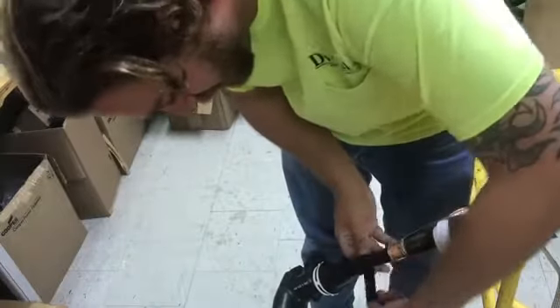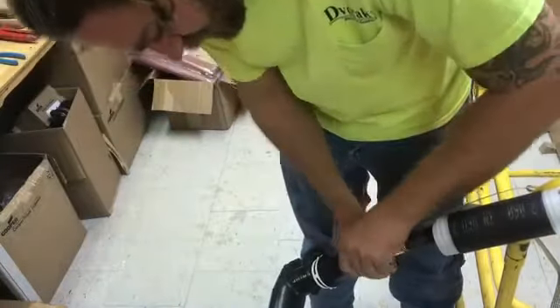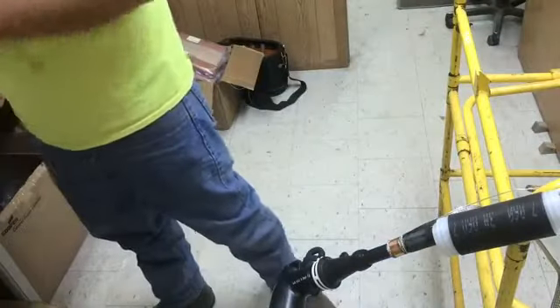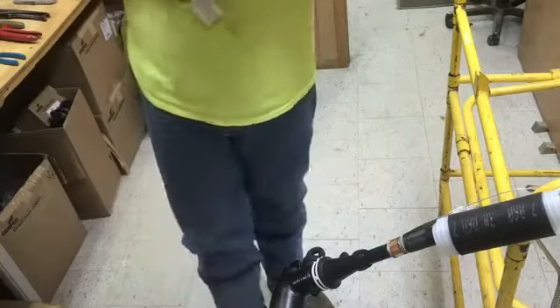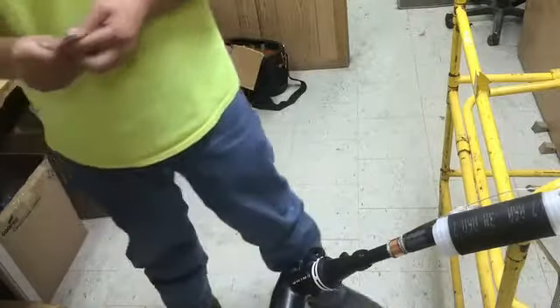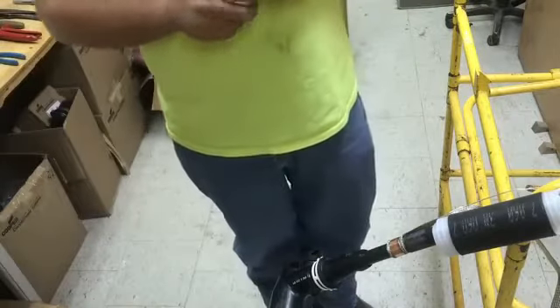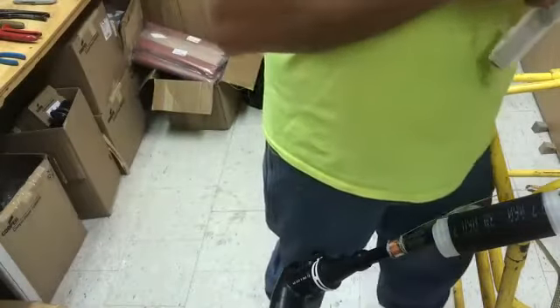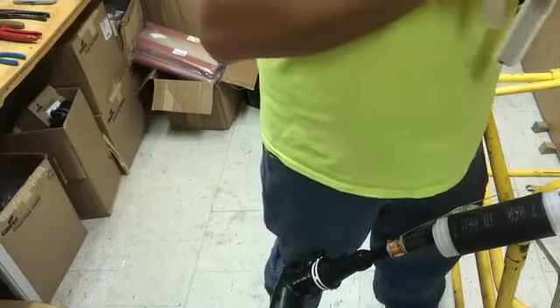Install the sealing mastic. The sealing mastic will be installed on the end of the 200 amp boot as well as the end of the cable jacket. One wrap needs to be installed underneath of the ground braid under the solder block, and another wrap installed over top of the ground braid over the solder block.